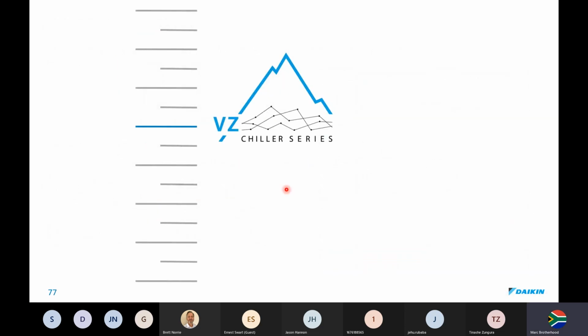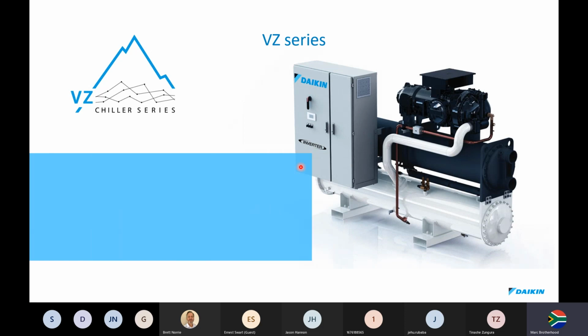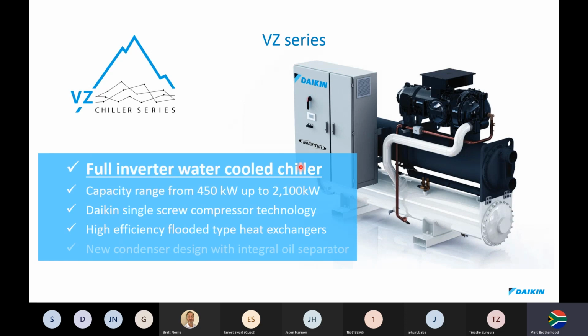Now we're going to look at the core focus once again. Daikin's core focus is inverter. And here we see the VZ series chillers. So these are fully inverter, water-cooled chillers, 450 kilowatts up to 2.1 megawatts. We use, once again, Daikin single screw compressors. Actually, all our screws are single screws. We don't have twin or triple screws. Also, if we did, they'd be very, very noisy.